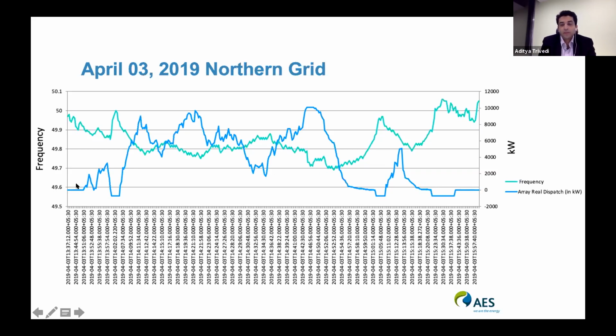What we are trying to prove here is that batteries are fast and they can respond instantaneously. Because this is a very small asset, just 10 megawatt on a huge grid, it was not showing any results in the frequency. But had there been sufficient capacity on the grid, this issue would not have been there, and the batteries would have been able to address it at the very beginning, and we would have had a much flatter frequency.